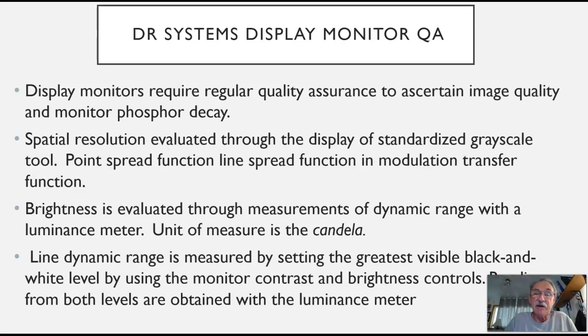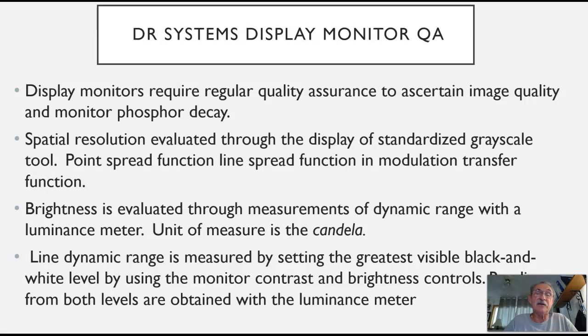DR systems display monitor: our radiographic images show up on soft copy monitors, so display monitors require regular quality assurance to ascertain image quality and monitor phosphor decay. Just like our X-ray room, the monitors do not last forever. Spatial resolution is evaluated through the display of the standardized grayscale tool. Point spread function, line spread function, and modulation transfer function can also be evaluated through these tools. The brightness of the image is evaluated through measurements of dynamic range with a luminance meter, which takes a reading right off of the monitor. The unit of measure for luminance off the monitor is called the candela.